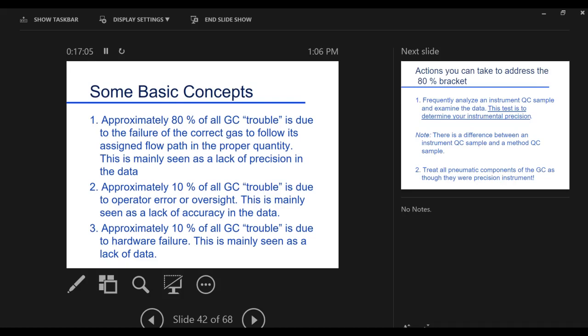And it probably shouldn't be a surprise, but 80% of the time we have problems, it's a plumbing problem. You know, the gas isn't going the right direction at the right speed. It's not what we wanted. And so a good person for gas chromatography is also a good plumber. You can fix the plumbing at home just like you can fix it in the gas chromatograph. And so getting that gas to go the right direction at the right quantity is 80% of the problem. Because it leaks someplace, a poor connection. That gives you trouble.